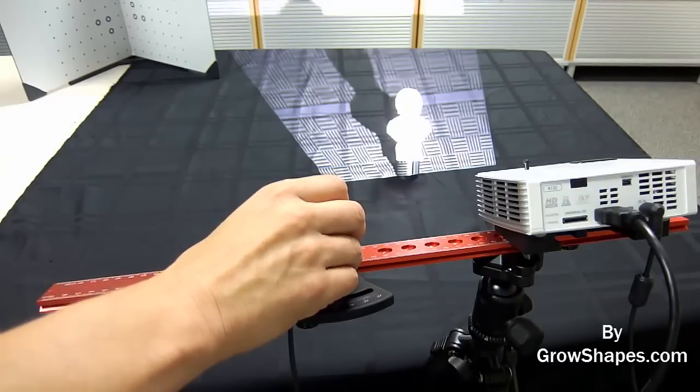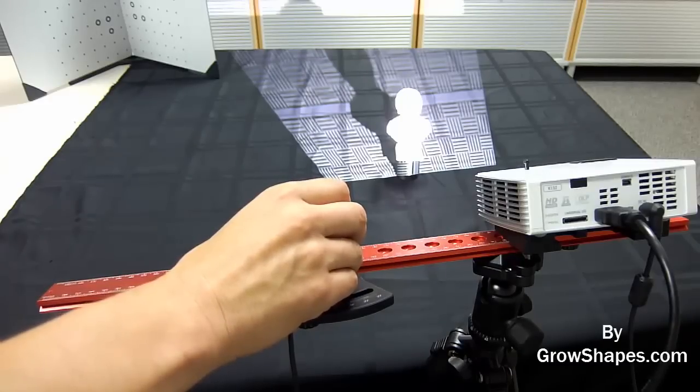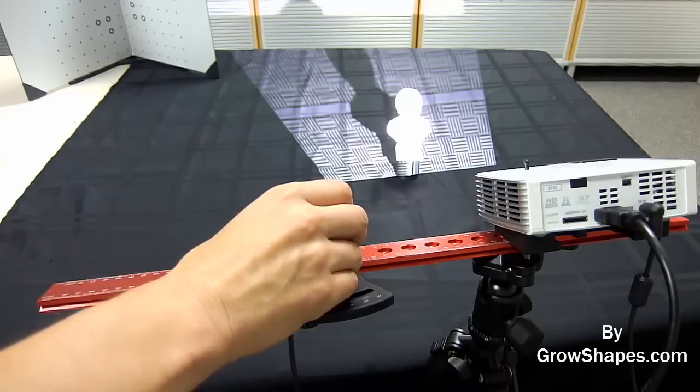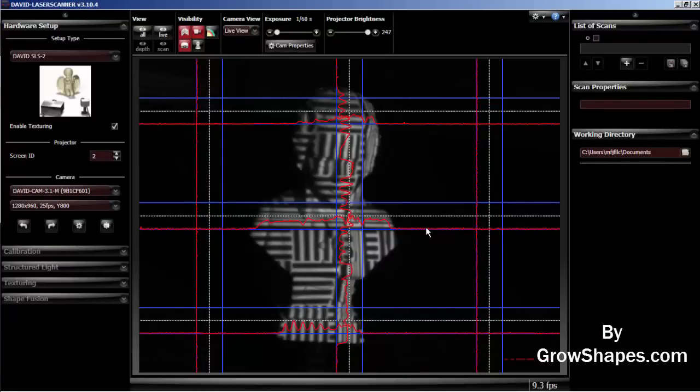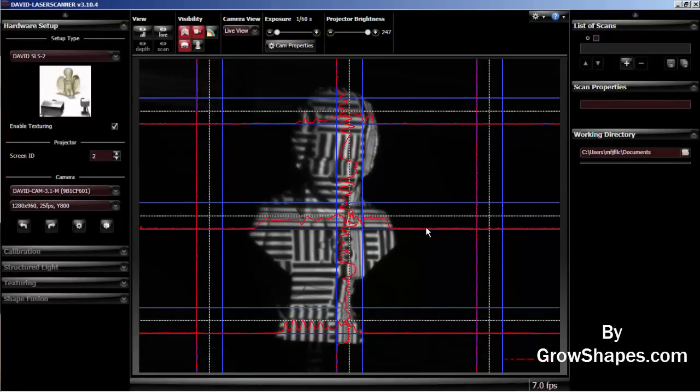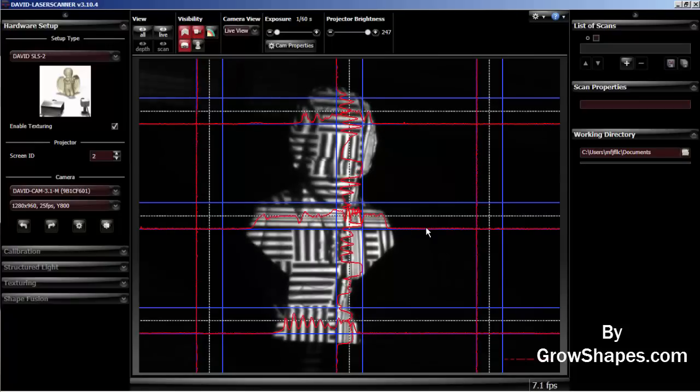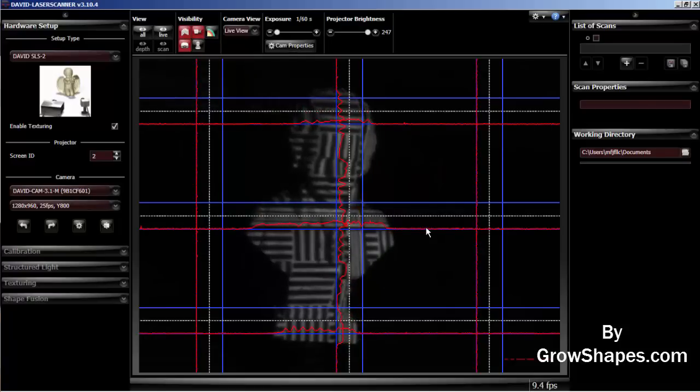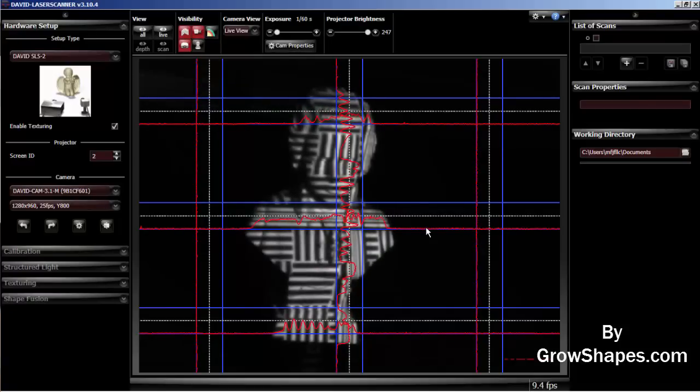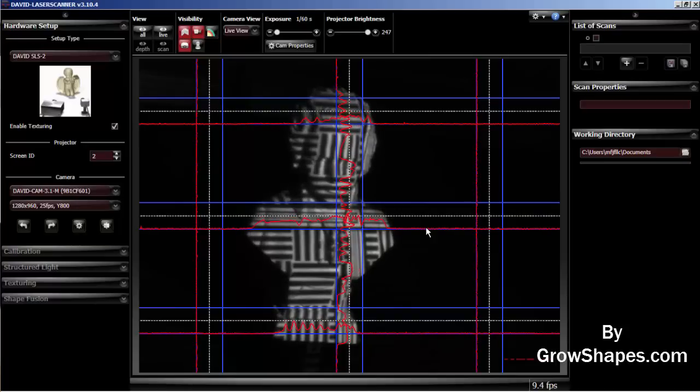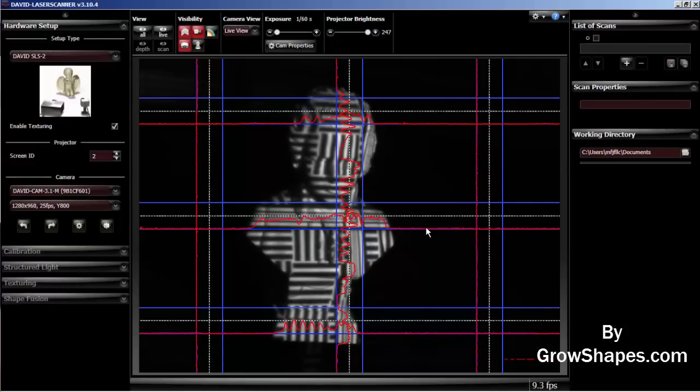Now it's time to set the aperture on the camera using the second ring. You need to look at the camera view image while adjusting the aperture. The red intensity curves must be sinusoidal and should not be under nor over saturated. That is, the red sine waves should not be cropped by the blue lines. The aperture is the only adjustment that can be made after completing the calibration and during the scanning process.